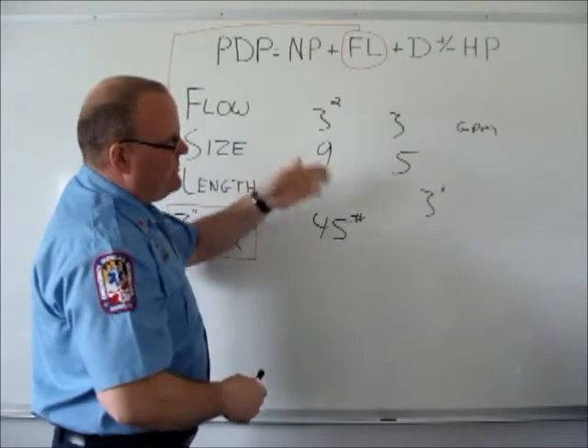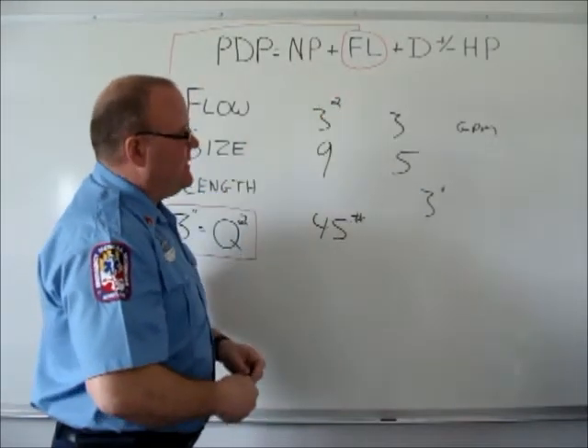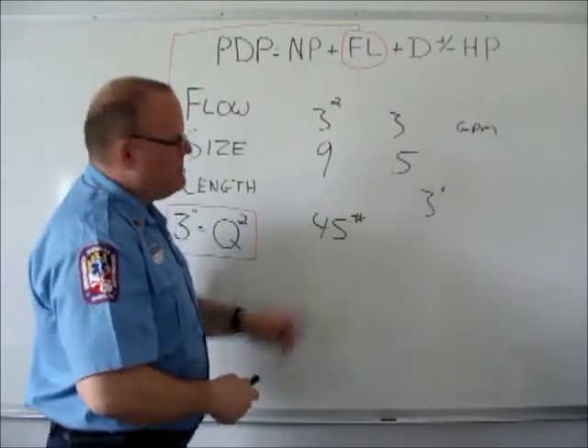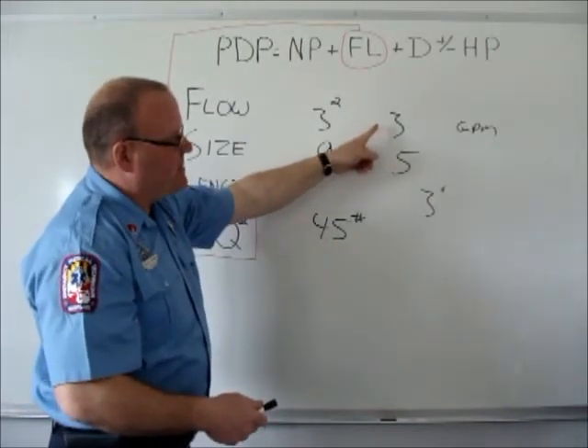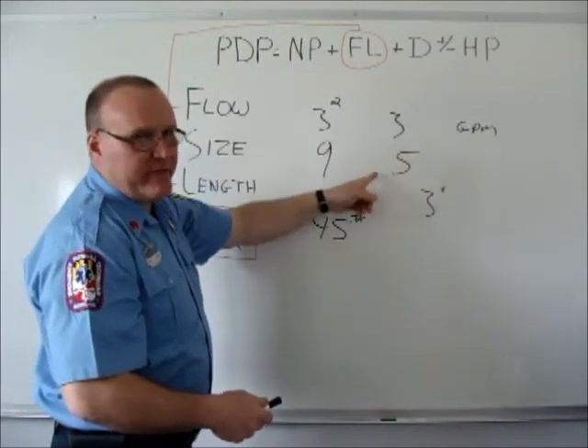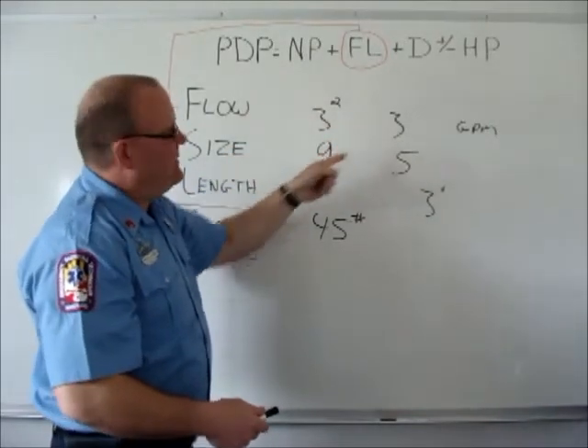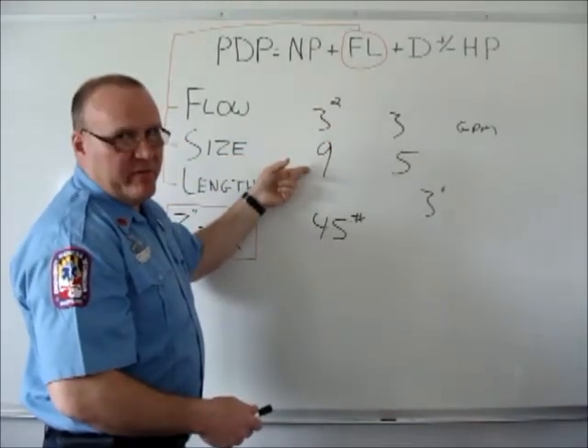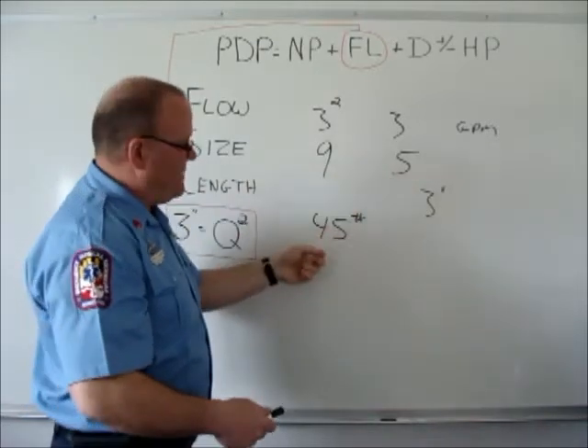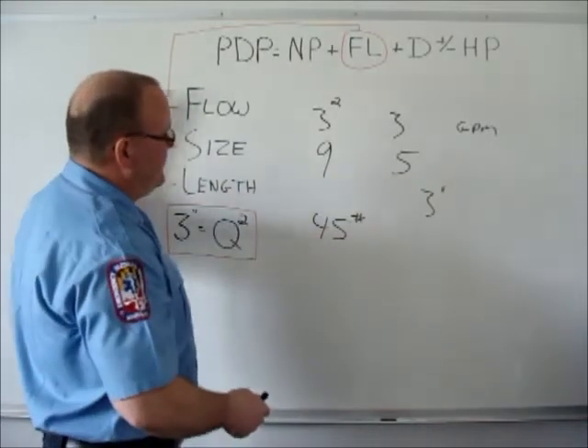So using this method, you could change the numbers around. Any numbers that you use, same thing. Divide by 100 for the gallons per minute and for the length, and then square the number that you come up with for the gallons per minute. Whatever number you end up with, multiply times the length, and that would give you your total friction loss. So flow, size, and length.